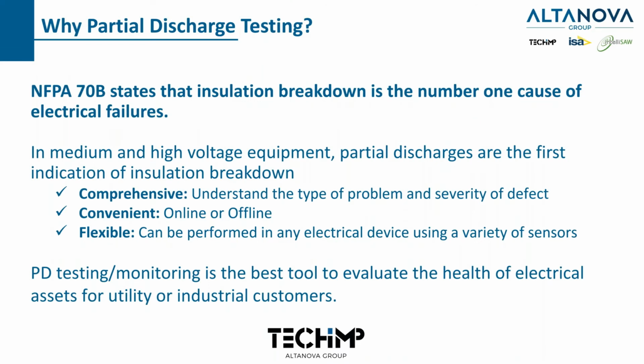Okay, National Fire Protection Association is an association in the U.S. Has stated that the number one cause of electrical failures is insulation breakdown. Okay, so the number one cause of failure is insulation breakdown. And the best test for insulation is partial discharge. Partial discharge is the best tool to evaluate the health of that insulation.